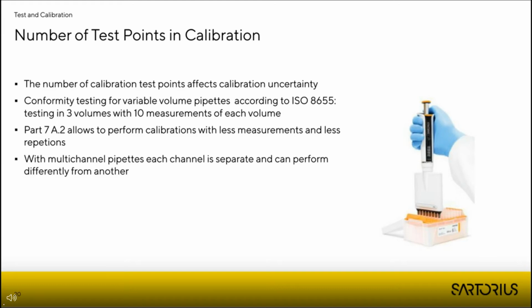Other measurement types than the 10.3 calibration, with fewer measurement points and fewer measurements per test point, are only possible when performing a test or calibration under Part 7A2 of the new ISO. Here it is, for example, possible to perform a 5.3 calibration, which would mean that you do only 5 measurements at 3 volumes, or a 10.2 calibration, which would mean 10 measurements at 2 volumes.